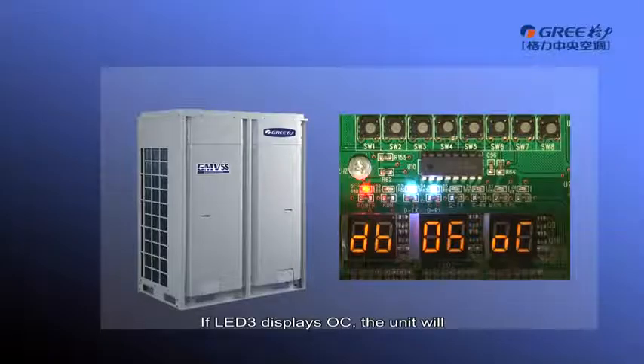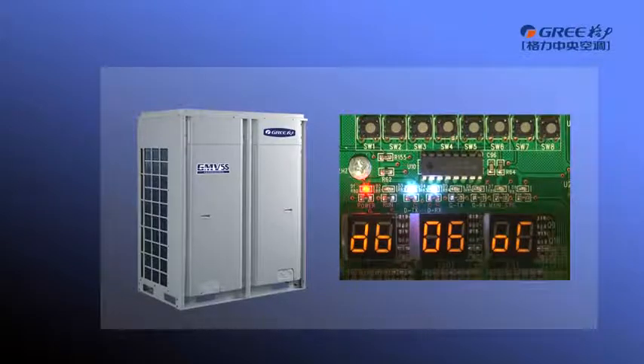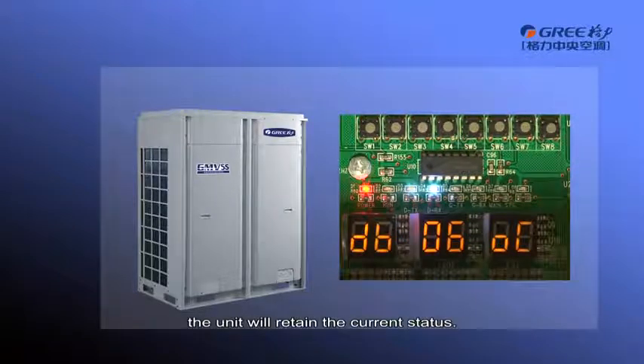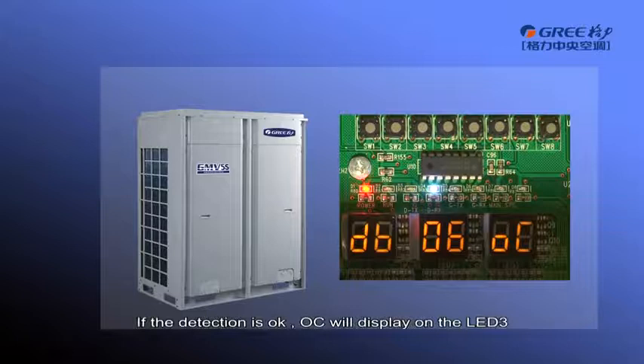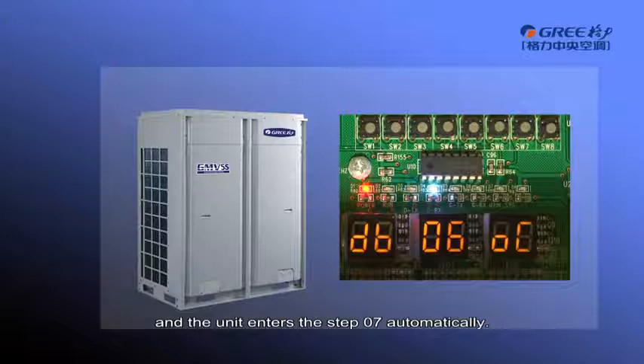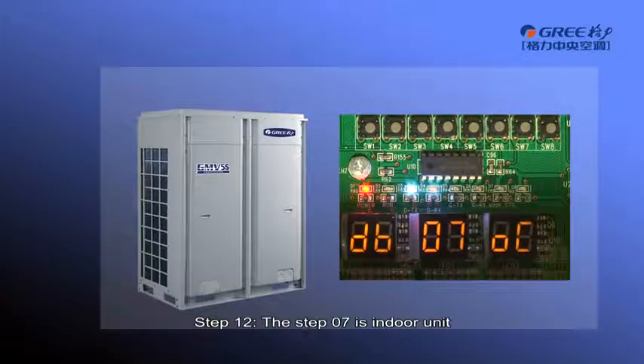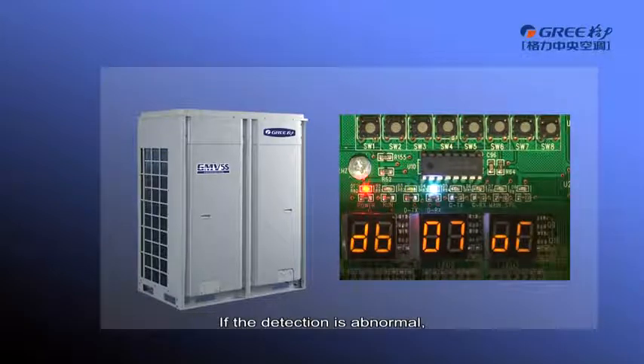If LED 3 displays OC, the unit will enter the Step 6 automatically. Step 11. The Step 6 is outdoor unit electric component detection. If the detection is abnormal, the unit will retain the current status. If the detection is OK, OC will display on LED 3 and the unit enters the Step 07 automatically. Step 12. The Step 7 is indoor unit electric component detection. If the detection is abnormal, the unit retains the current status.